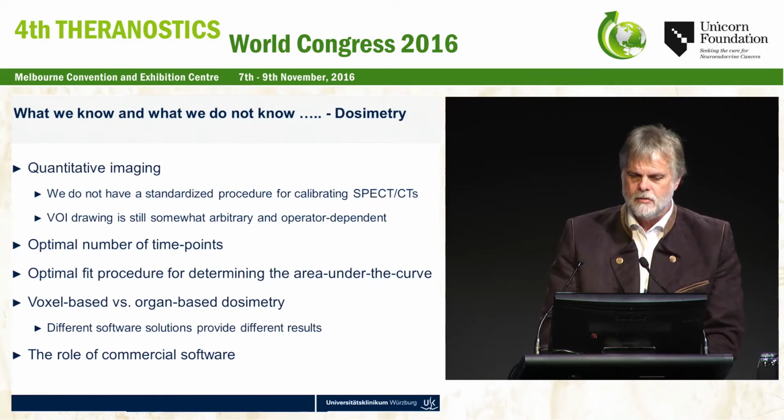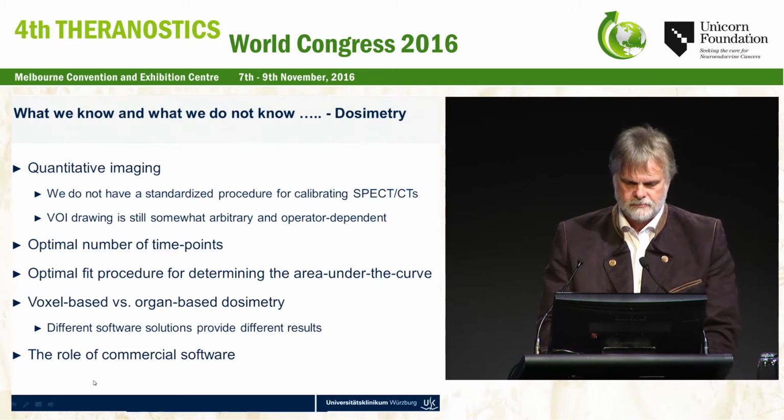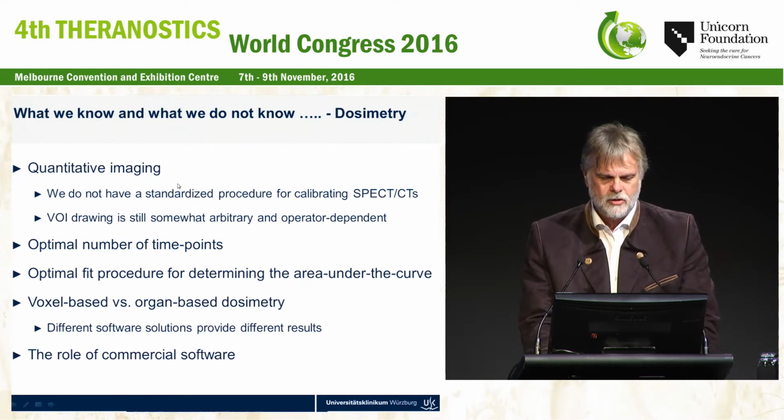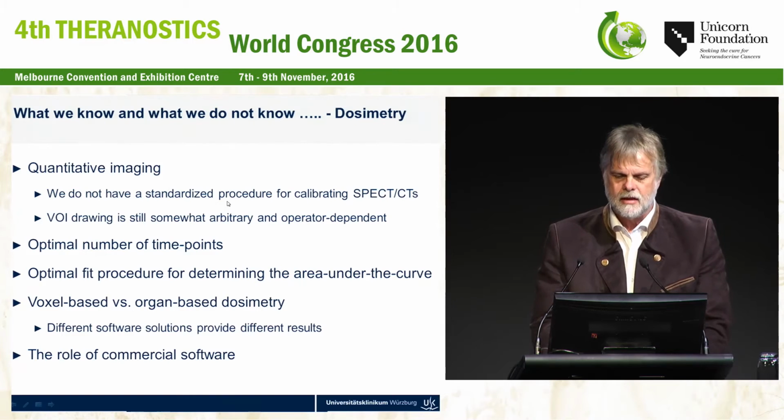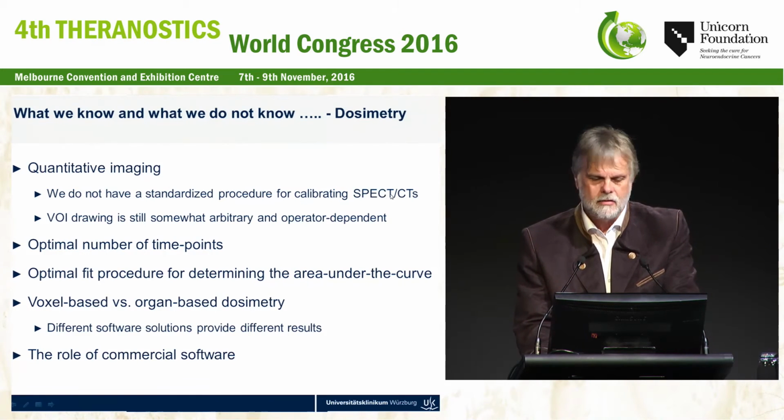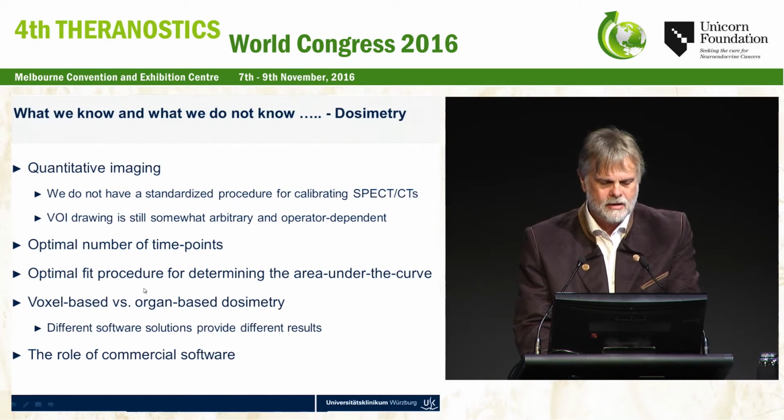So, what we know and what we do not know on dosimetry. We have quantitative imaging, but we do not have a real standardized procedure for calibrating SPECT-CTs and gamma cameras. This is just not the case. The VOI drawing is also somewhat arbitrary. We have to think about the optimal number of time points for scanning, and my recommendation is always to try to go for more than 4. Optimal fit procedure is also a matter of debate. It's not so easy sometimes.